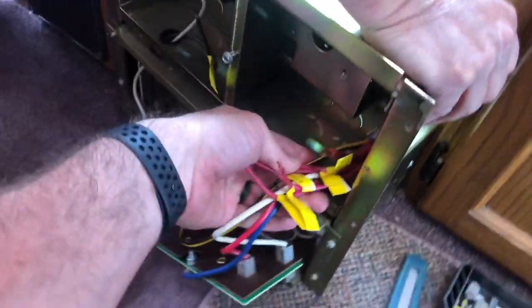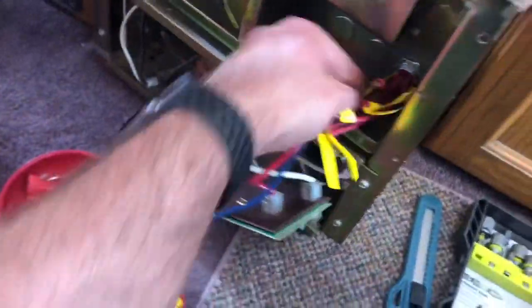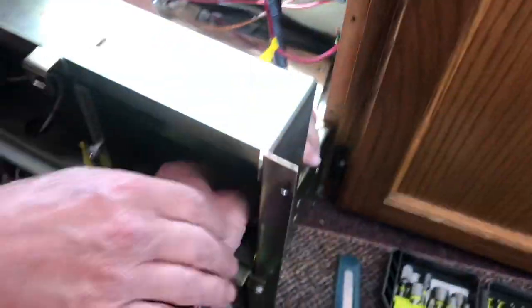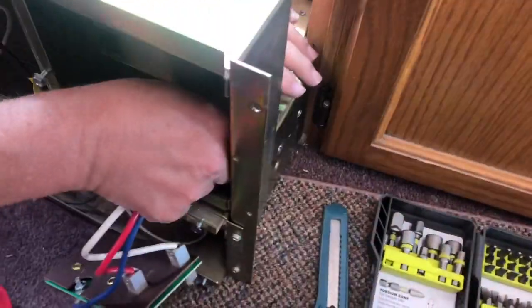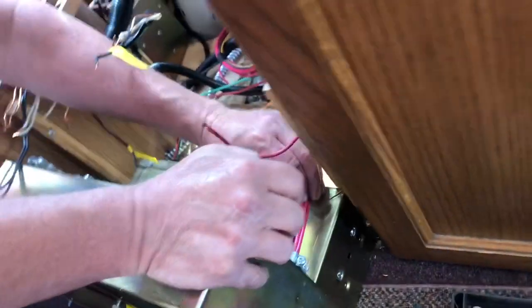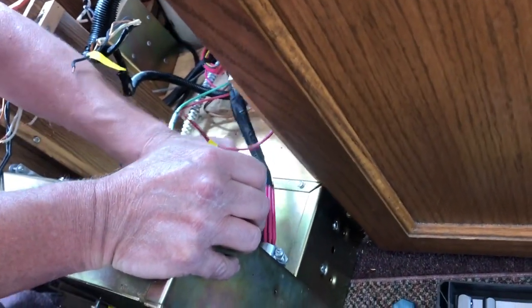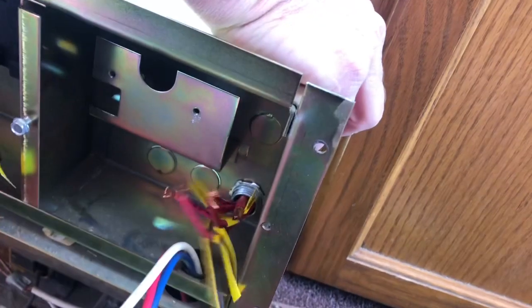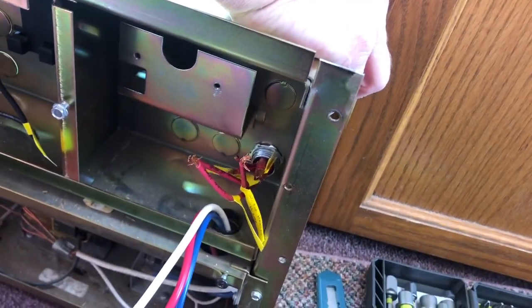Got that ground out on the DC side. We're gonna go ahead and start yanking those DC wires through there. Looks like thus far, knock on wood, all those tags have lasted getting through the conduit. I'll do them one at a time so I don't mess up those tags. I mean, we got those labeled anyway, but yeah. There's your spare for something.